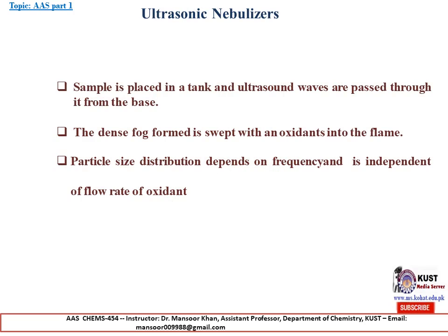Now another one is ultrasonic nebulizers. The ultrasonic nebulizer is another type of nebulizer. The sample is placed in a tank and ultrasound waves are passed through it from the base. In a pneumatic nebulizer, a gas does the nebulization, while in an ultrasonic nebulizer, ultrasonic waves do the nebulization. The dense aerosol is swept with an oxidant into the flame. Particle size distribution depends on the frequency and is independent of the flow rate of the oxidant.